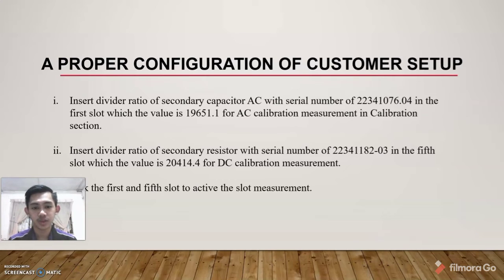So before we run the measurement, we need to apply a proper setting of customer setup, which requires some configuration of calibration in calibration section. In calibration section, we need to insert the divider ratio of secondary capacitor AC in the first slot, which the value is 19651.1. That is for AC calibration measurement. Then we insert the divider ratio of secondary resistor in the fifth slot, which the value is 20414.4 for DC calibration measurement. After that, we need to tick the first and fifth slot to activate the slots measurement.